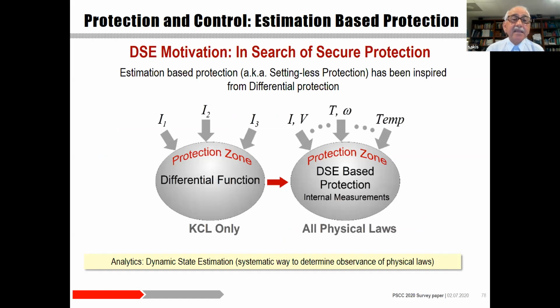Basically, it is inspired by the differential protection function. All the differential protection function does is look at the device to be protected and monitor the sum of the currents into the device. Utilizing the generalized Kirchhoff's current law, the currents have to sum to 0, and if they do not, then there is an internal problem in the device, and we trip the device. Now, differential protection is one of the most secure protection functions we have in power systems. On the other hand, it does not cover all the possible faults that can happen in the power system.